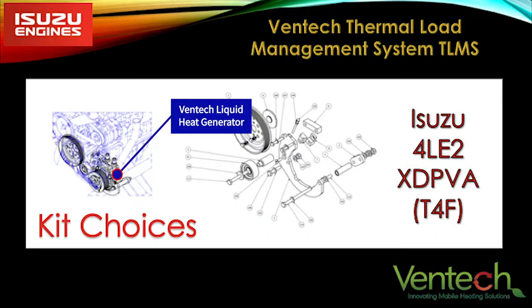The heart of the thermal load management system is the Ventech liquid heat generator model 700. This compact heat and load generator is belt-driven and controlled by an onboard digital controller for aftermarket installations, and can be controlled directly by the generator controller for OE factory installations.